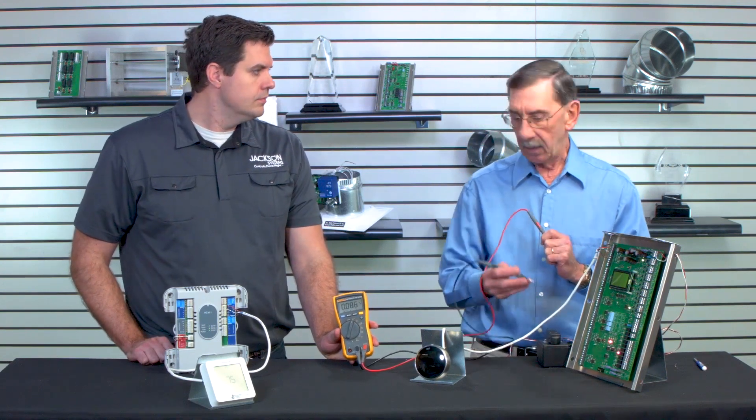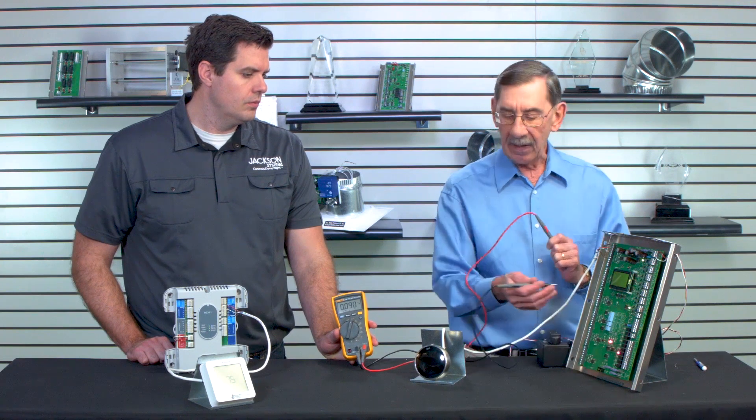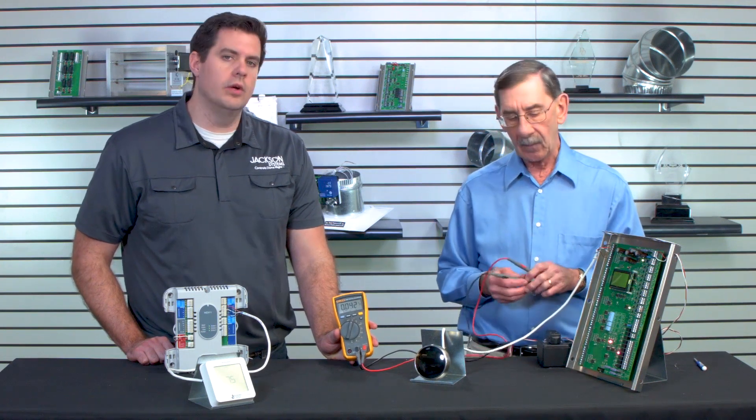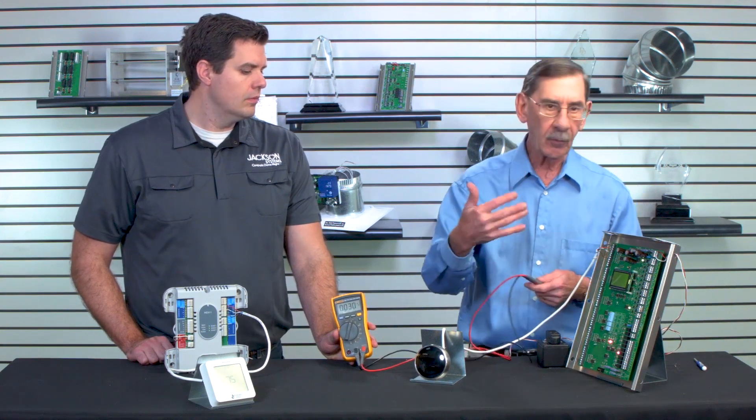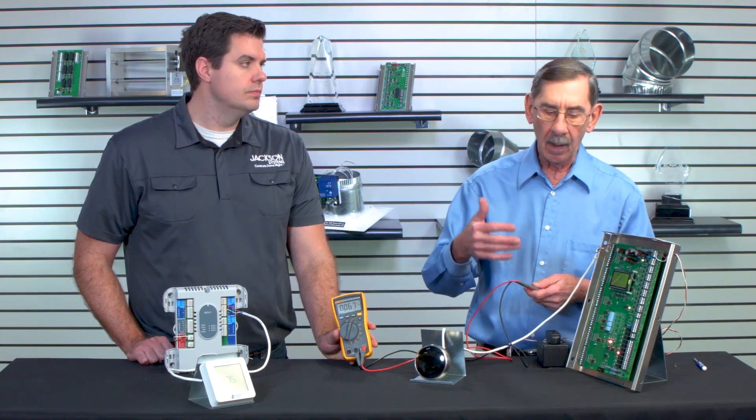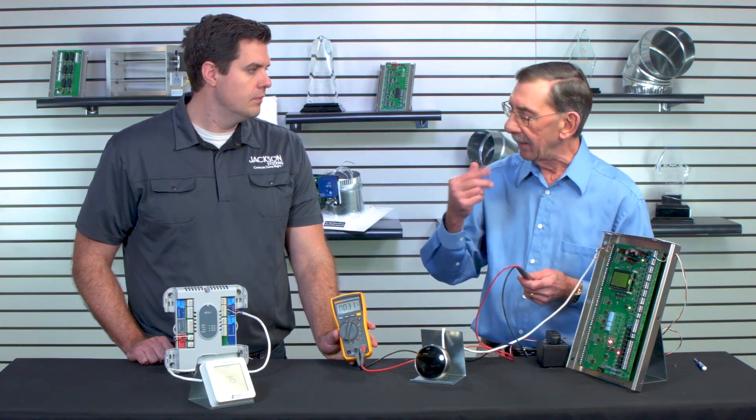Now we've got, we know we've got an input. The panel is telling us that it's received that call. It has energized the output to the equipment. Well, we're not using the equipment transformer to power the panel or the thermostats or even the zone dampers. We use a separate transformer. So all we are over here again is a switch.